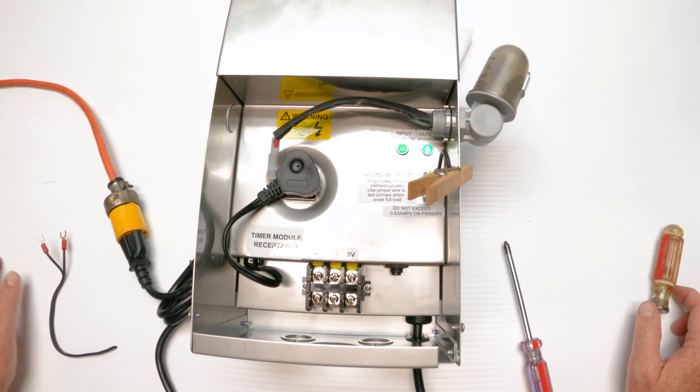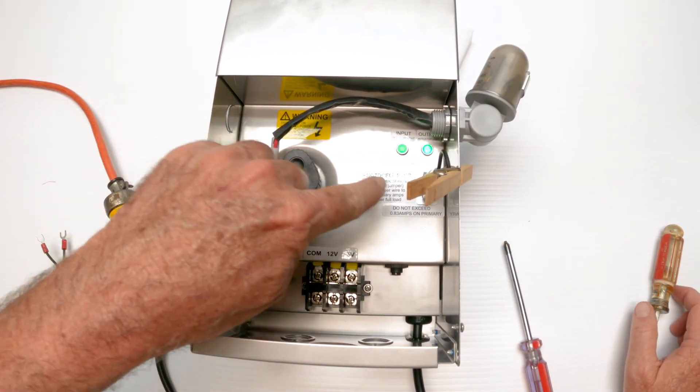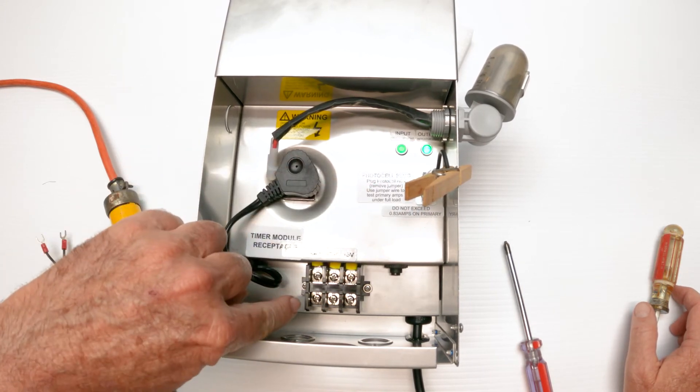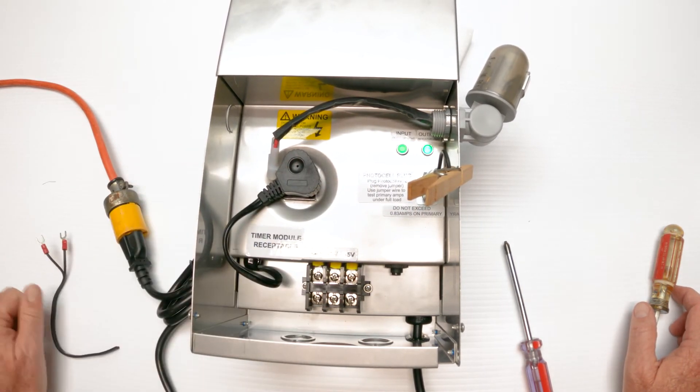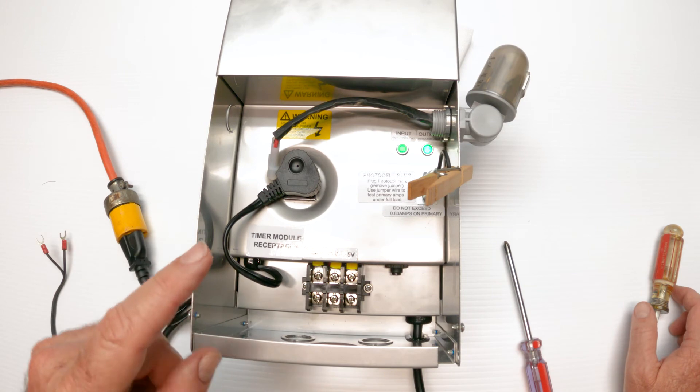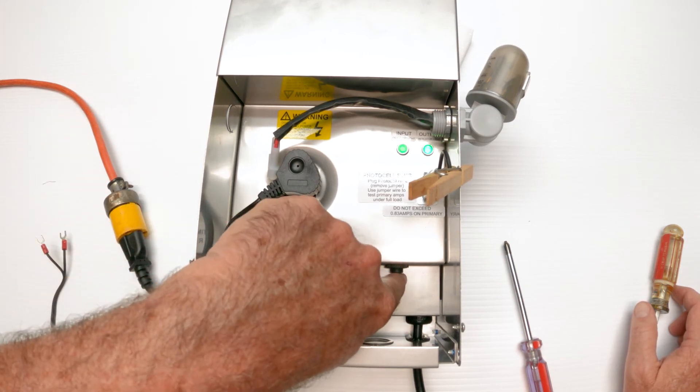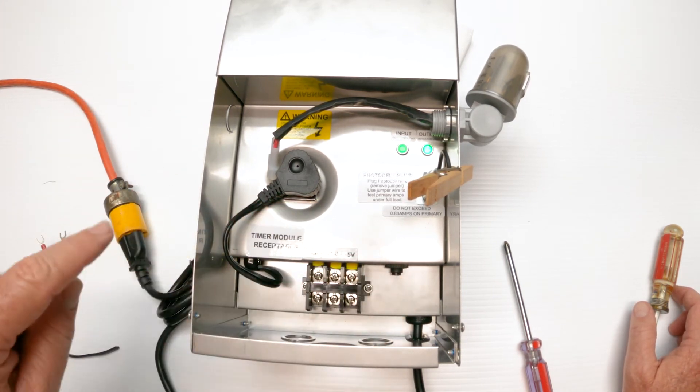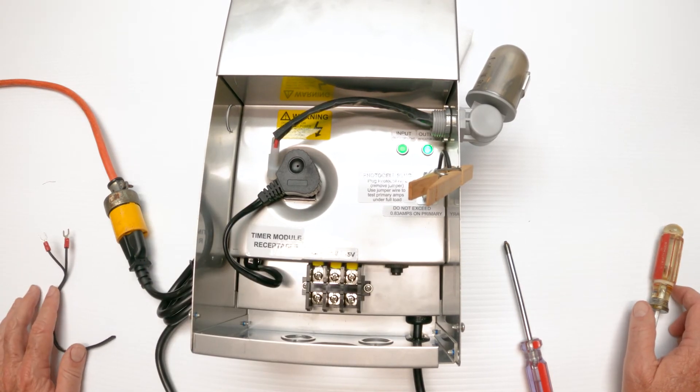What this tells me is the transformer works with the variables removed. So the problem was possibly the timer, possibly the photo cell, or possibly there's a short out in the field. If there's a short out on the field, most likely this little circuit breaker would have popped and you'd have to push it in. It's a great indicator if there's a problem in the field.